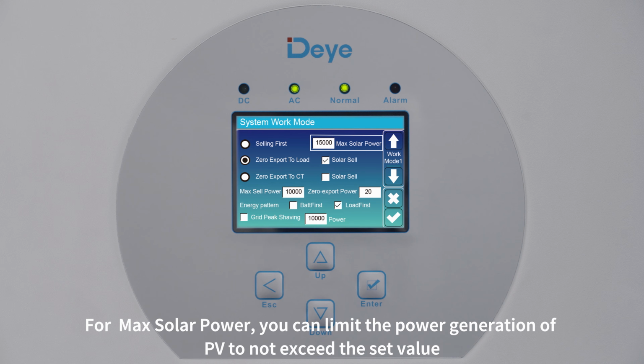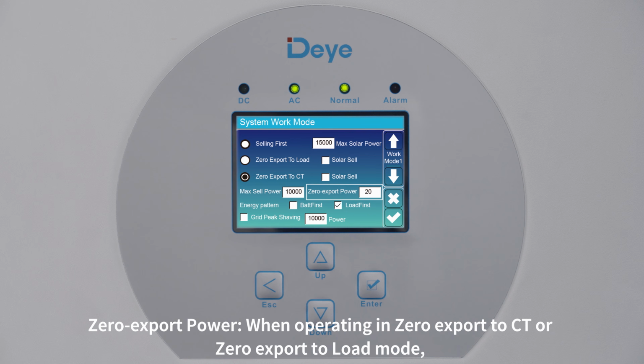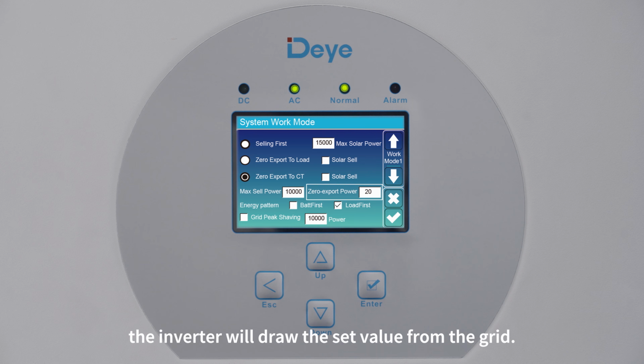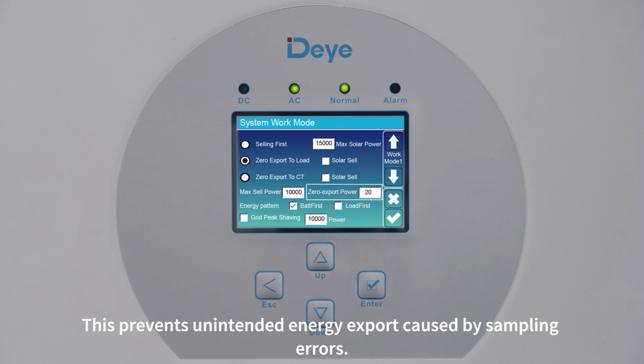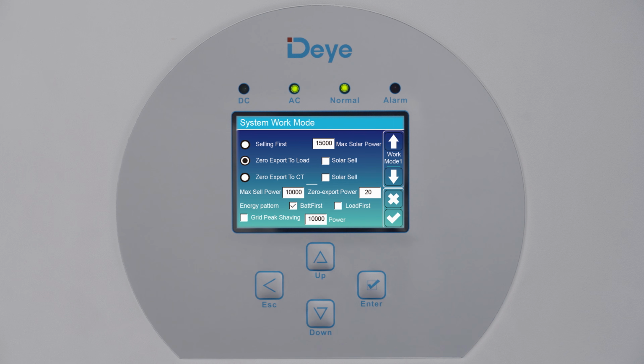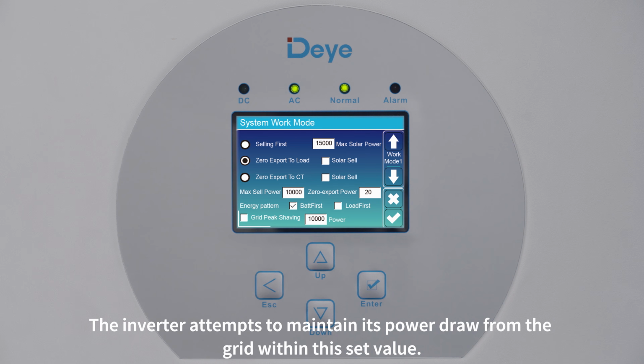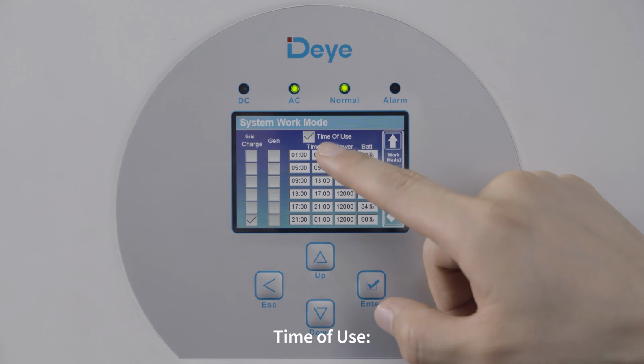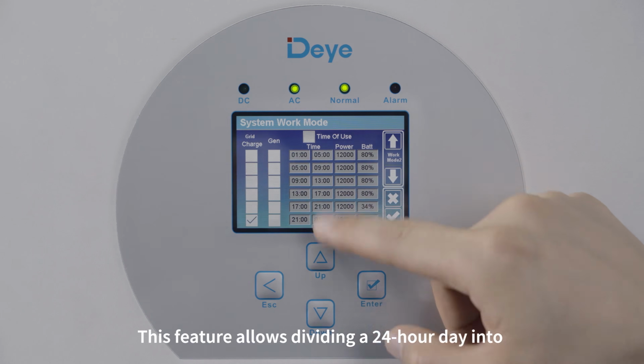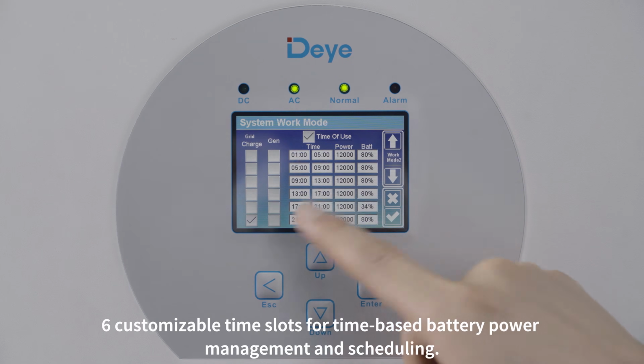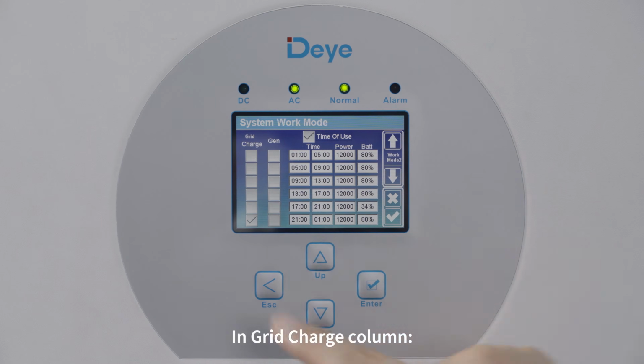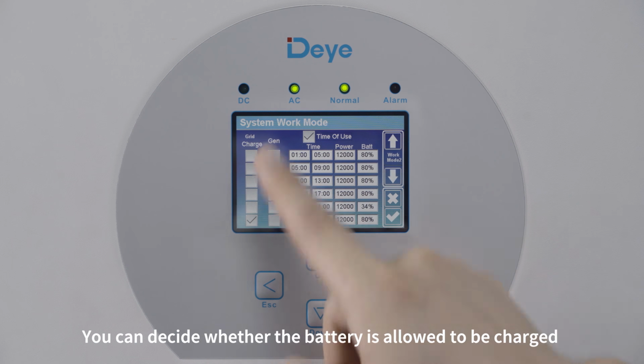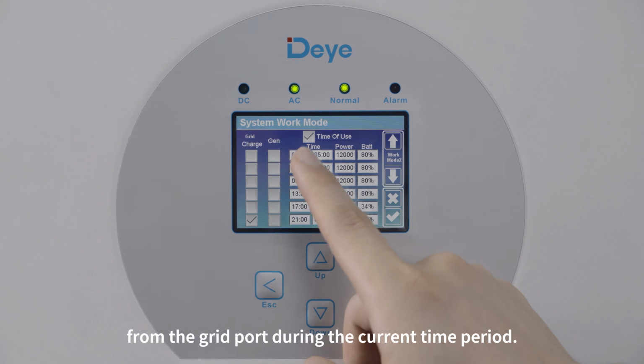For max solar power, you can limit the power generation of PV to not exceed the set value. When operating in zero export to CT or zero export to load mode, the inverter will draw the set value from the grid. This prevents unintended energy export caused by sampling errors. Grid peak shaving: the inverter attempts to maintain its power draw from the grid within this set value. Time of use: this feature allows dividing a 24-hour day into 6 customizable time slots for time-based battery power management and scheduling. In grid charge, you can decide whether the battery is allowed to be charged from the grid port during the current time period.